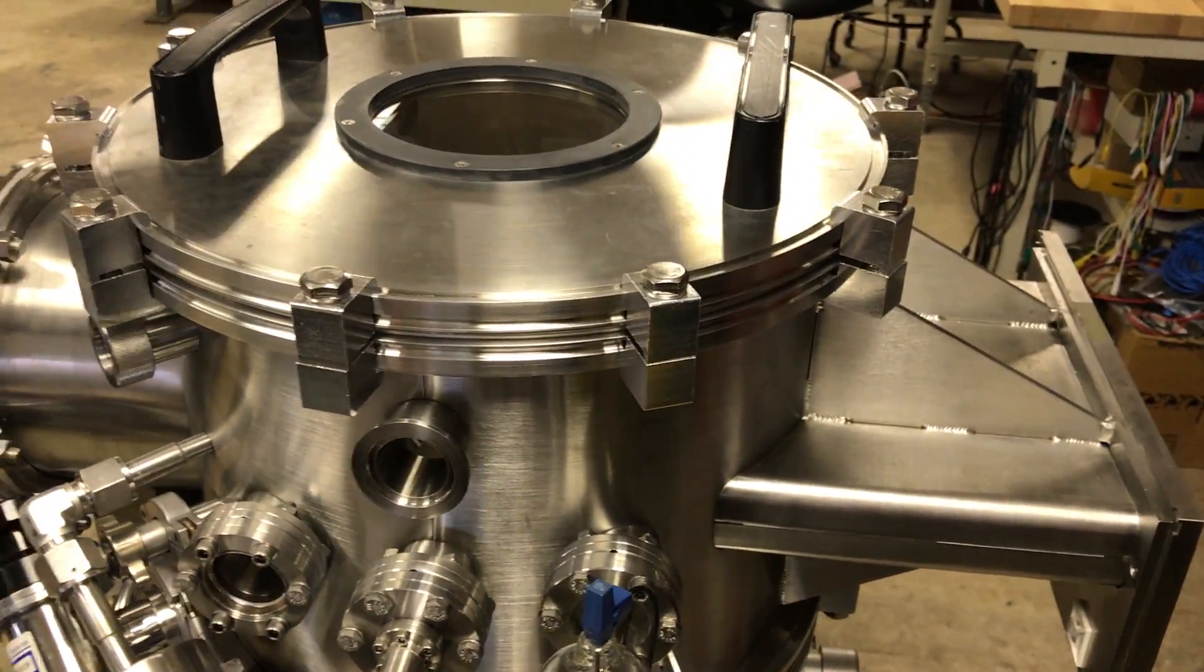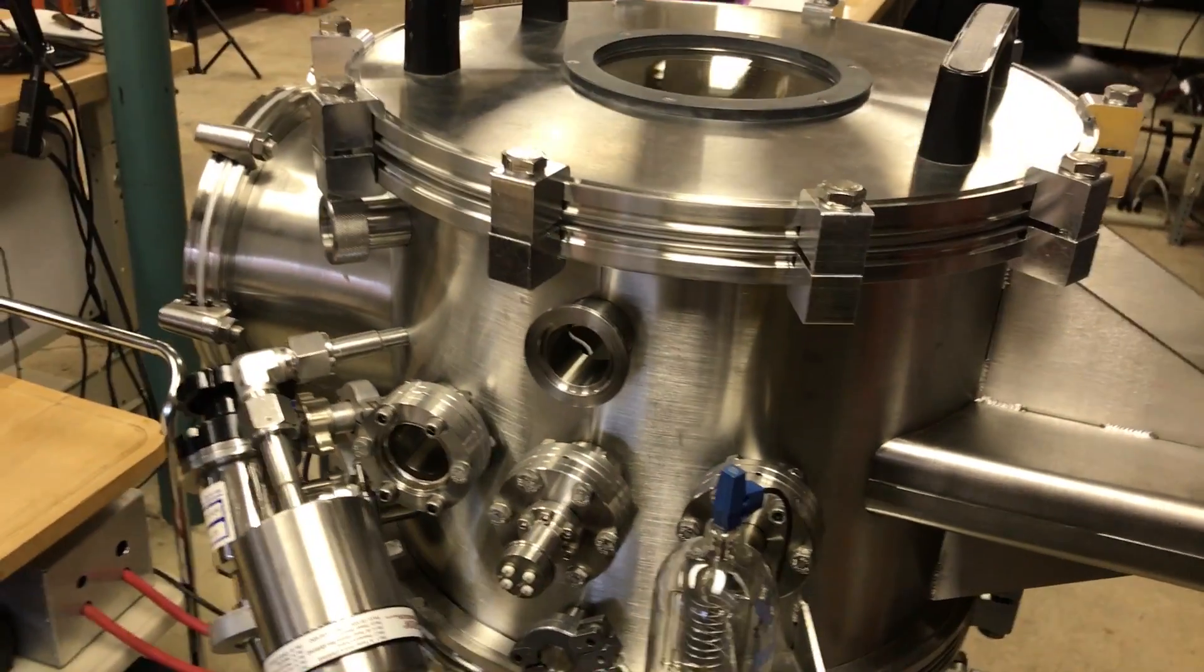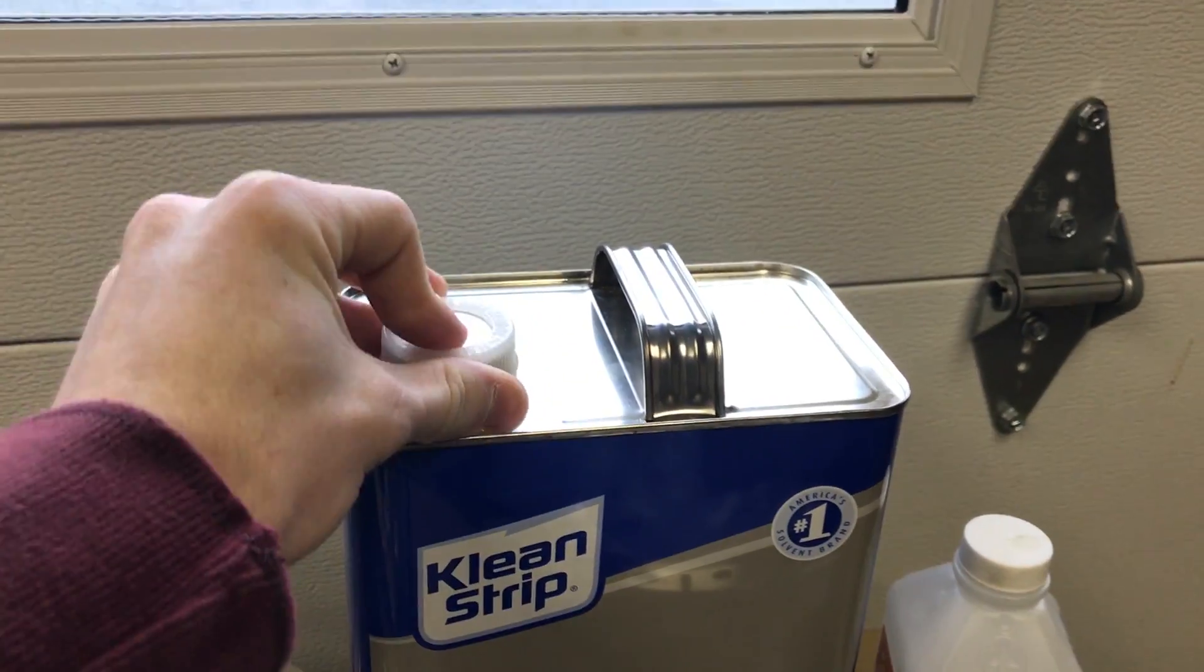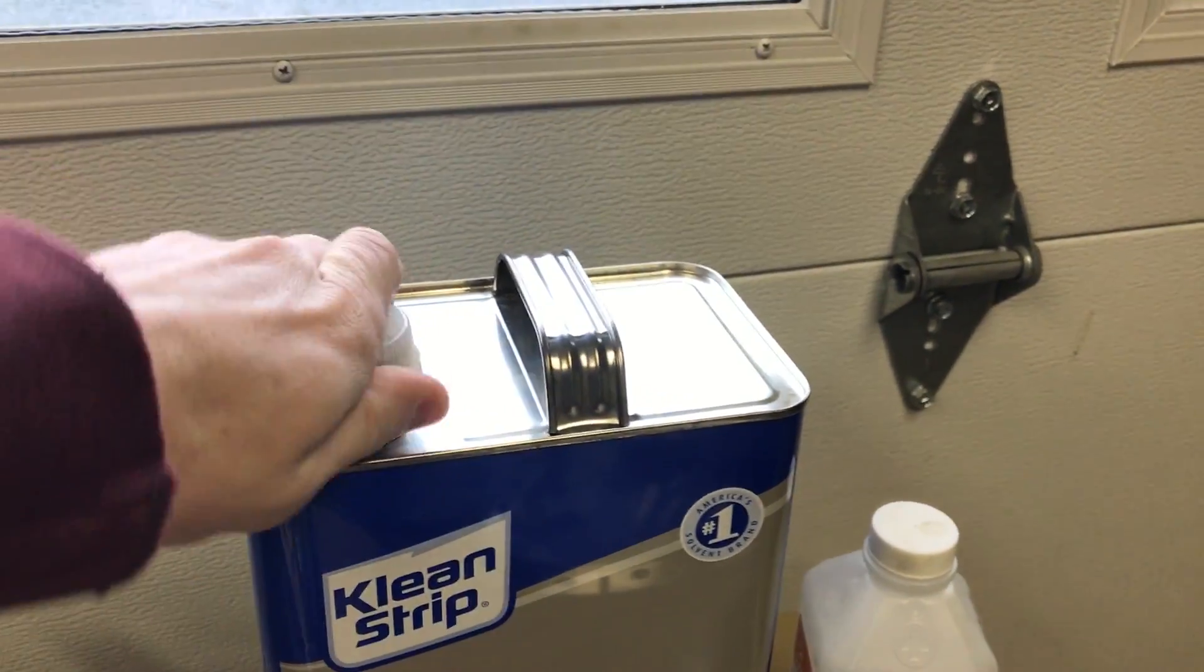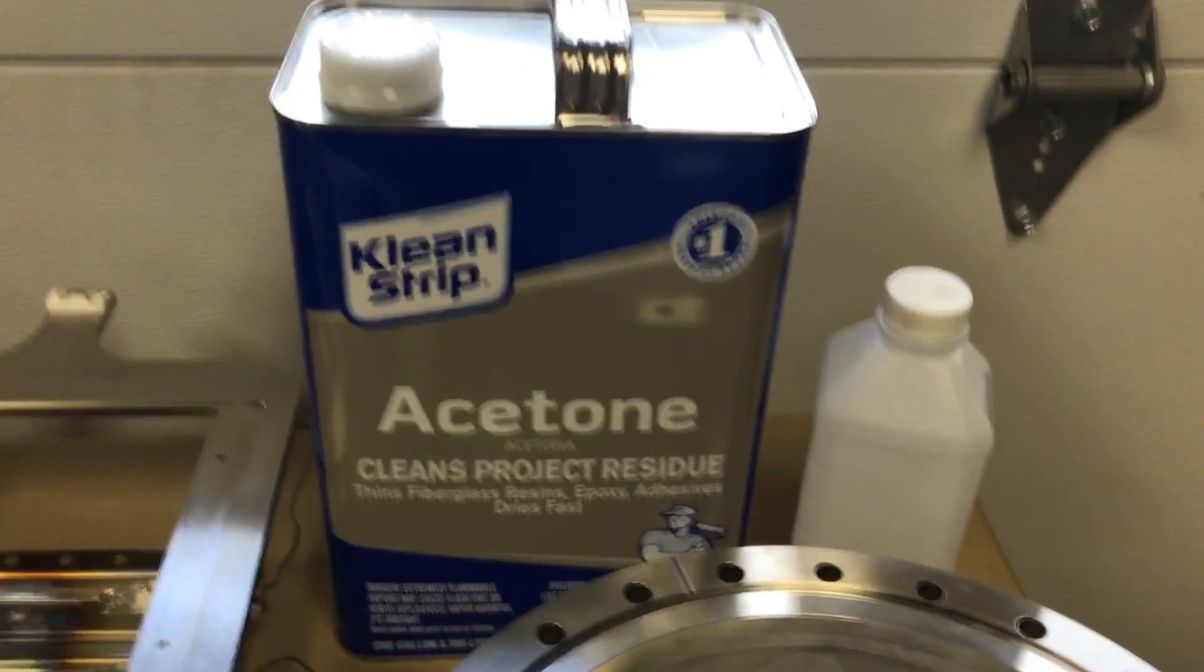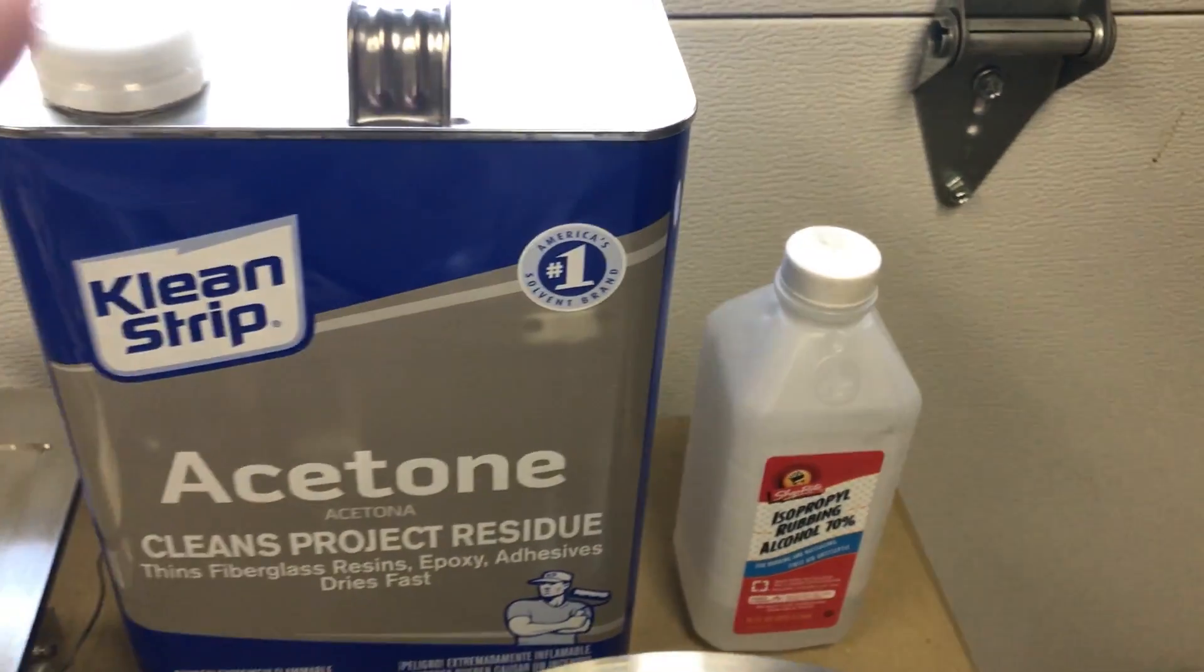If you want to get in the 1x10 to the minus 6 to the minus 7 and beyond torr range, you're going to have to do a pretty thorough wipe down of your chamber. The best thing to do, you can do an additional wipe down with acetone, and that will get rid of fingerprints and organics and stuff like that. And then after that, you want to do an isopropyl alcohol wipe down to get rid of the acetone residue.